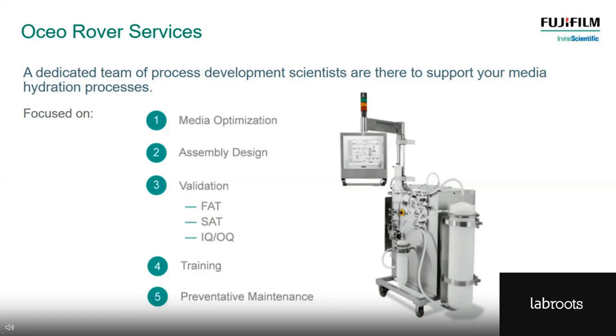We can also look at assembly design — you may want to change the assembly to accommodate some sampling regimes. But fundamentally, the assembly is what enables the process to work, so we won't be changing the flow paths and direction. Going into manufacturing, you'd look for support from us as the equipment vendor through the validation cycle — through the factory acceptance test, site acceptance tests, installation and operational qualification, and possibly support around performance qualification. Training and preventative maintenance are also important with any equipment.